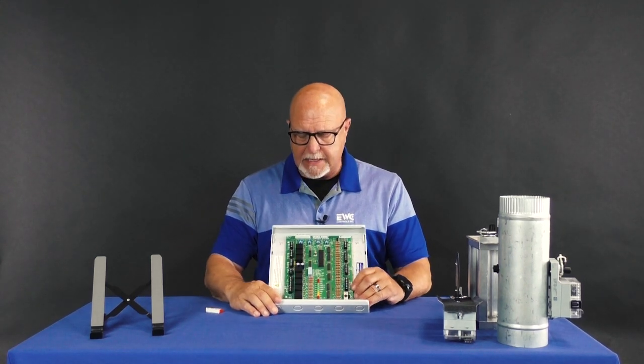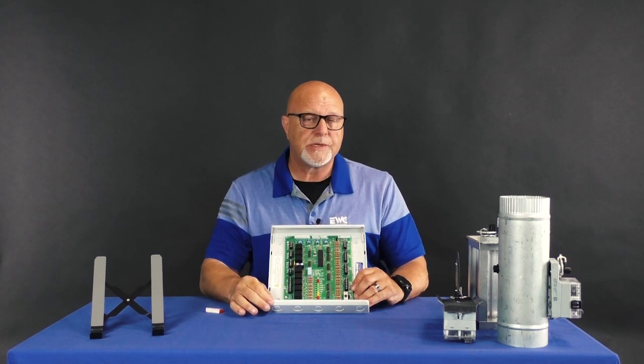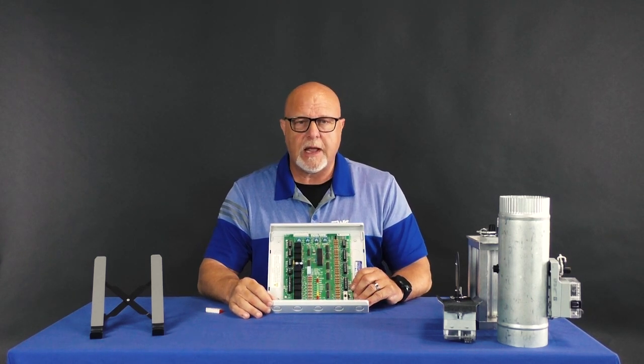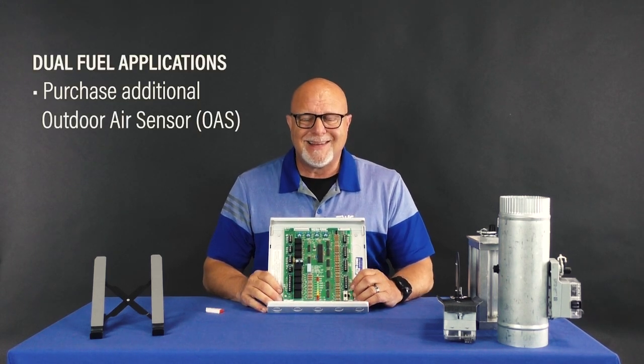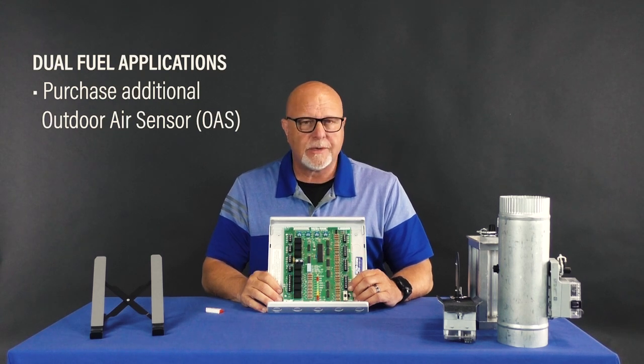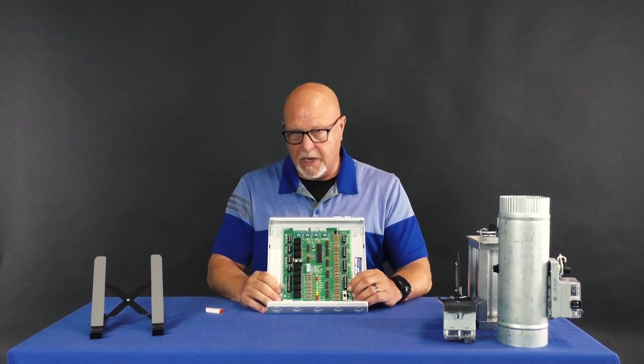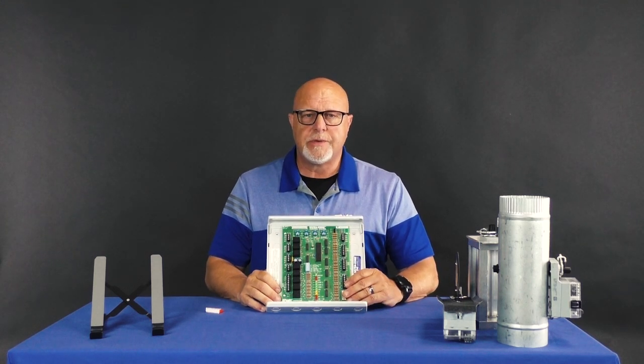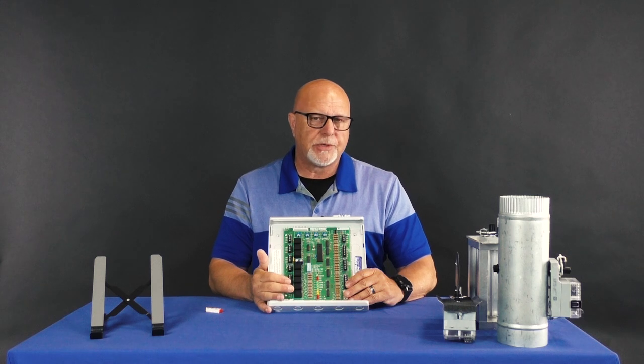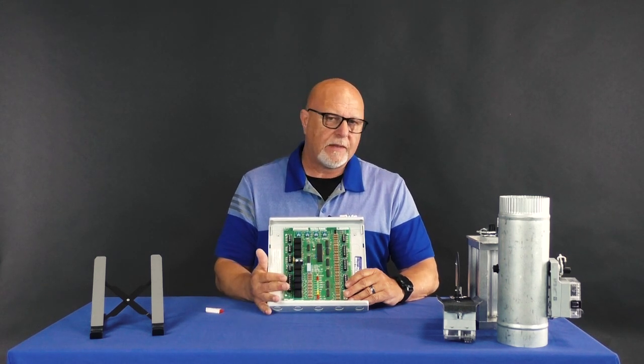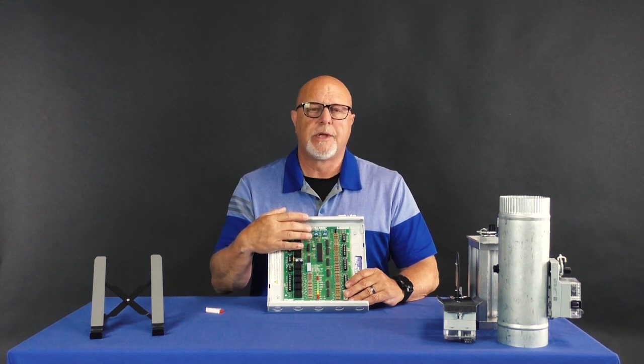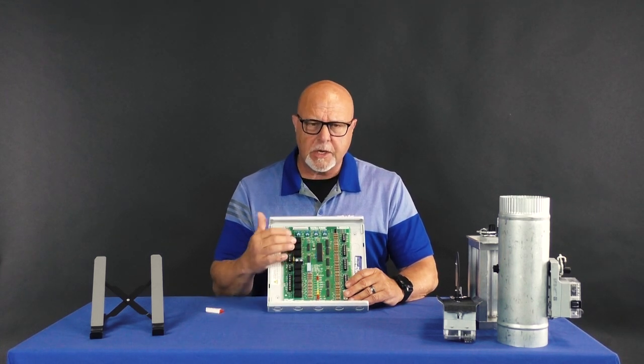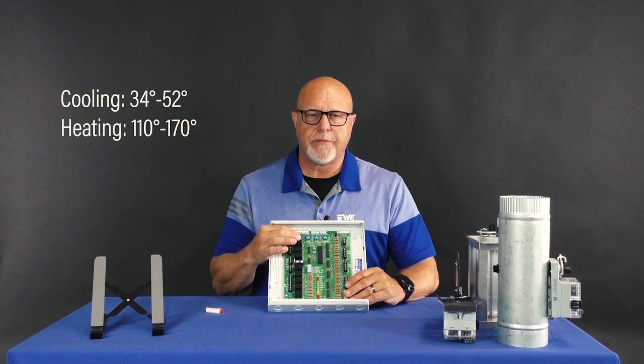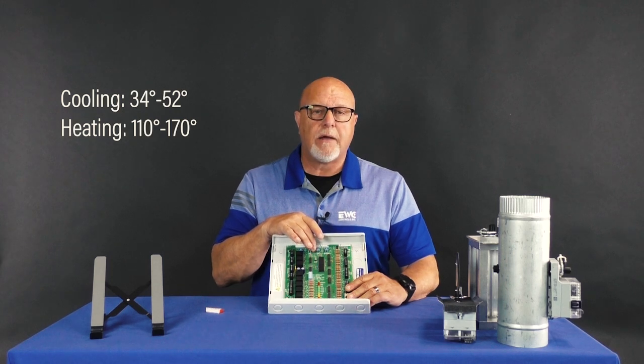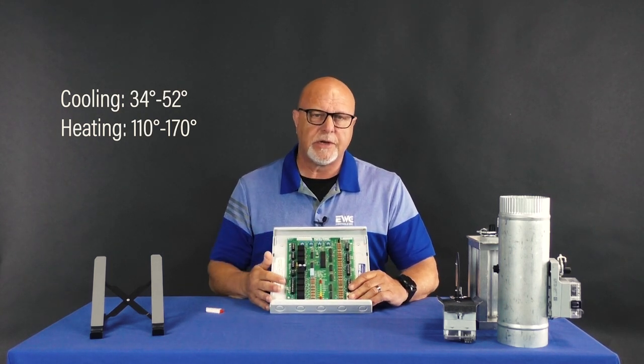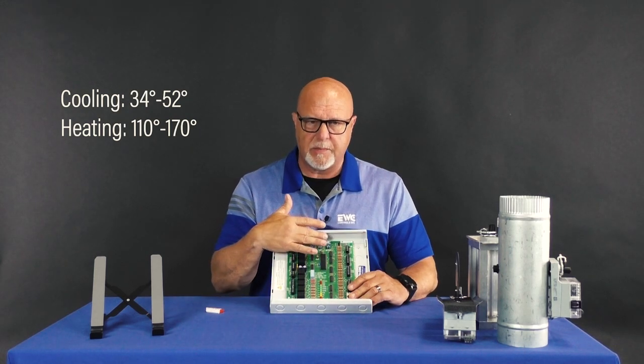The BM Plus, as I said before, will handle 3 stages of heat, 2 stages of cooling, heat pump, and dual fuel. In a dual fuel application, you will most likely want to purchase an additional OAS, which is an outdoor air sensor. Our supply air sensor is going to come with this board. That is needed to monitor our supply air temperature. In the event that it gets too hot or too cold, you will set your potentiometers to the settings that you desire. On the cold side, you will have a setting from 34 to 52 degrees, and on the heating, you will have a setting from 110 to 170 degrees in 1 degree increments, as you can see by the potentiometer dial.